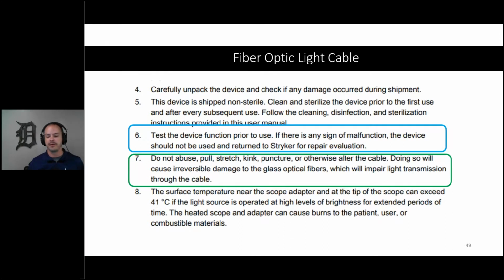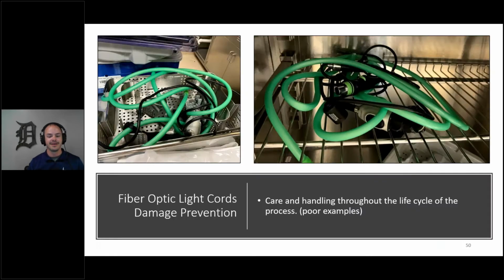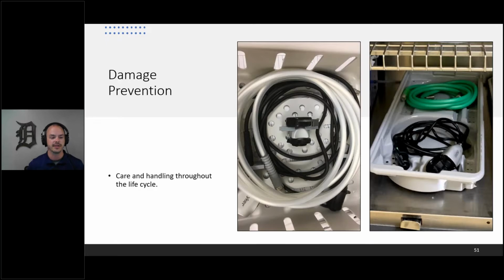But what about the instruction to not abuse, pull, stretch, or kink the cable? We've shown you pictures, and you'll see more, of how these things look in the real world, whether from the OR or in SPD—this is how we receive them a lot of times. Unfortunately, especially with the sheath on these light cords, they're not transparent, so even if we check them, we only have a small spot to check for integrity.